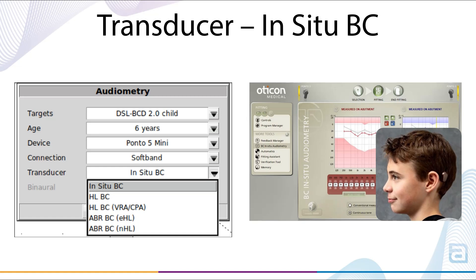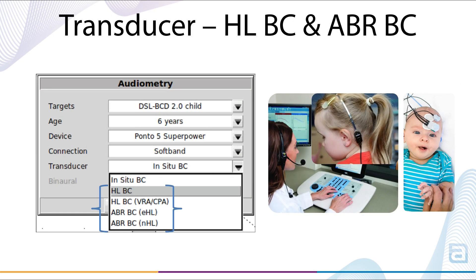Transducer sets how hearing thresholds were measured. In-situ is available for any connection type and uses hearing thresholds measured with the bone conduction device on the patient via pure tones produced by the bone conduction device and controlled from the hearing aid software. HL-BC options are for SoftBand and SoundArc fittings where in-situ thresholds cannot be measured, and hearing thresholds are bone oscillator dBHL. All HL-BC and ABR-BC transducer selections apply a skin transmission loss prescriptive target correction based on the patient's age.